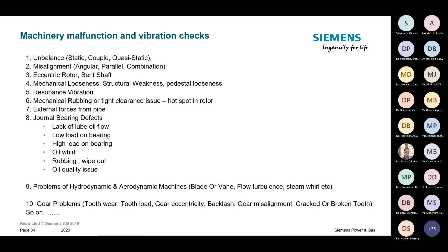Then how do you do it in real life? We typically use two proximity probes. The proximity probes are basically measuring the vibrations. They measure the AC and DC signals. The AC signal is the vibration, but the DC signal is the shaft centerline position. And then accelerometers are also used to measure the pedestal vibration of a stationary component. And then from that you can use relative, so this is absolute, then you have relative, or relative to absolute, whatever you can say. You can do it by using two separate probes.